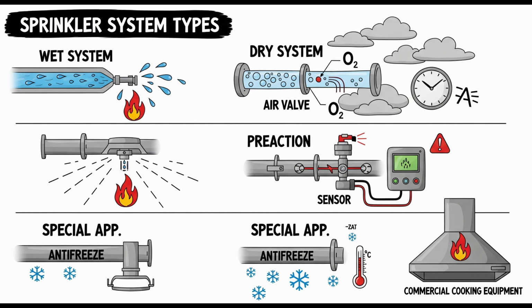How do you supervise the piping if it's normally dry? Usually with low-pressure air or nitrogen, typically around 7 psi or so for double and non-interlock systems. This supervisory pressure allows the system to detect leaks in the piping. A drop in this low pressure triggers a supervisory alarm before the main valve trips, signaling pipe damage or leak without causing an accidental water discharge. So the air pressure isn't holding back water, it's just checking the pipes are intact. Exactly. For non-interlock and double interlock systems, that's its primary purpose: integrity supervision.